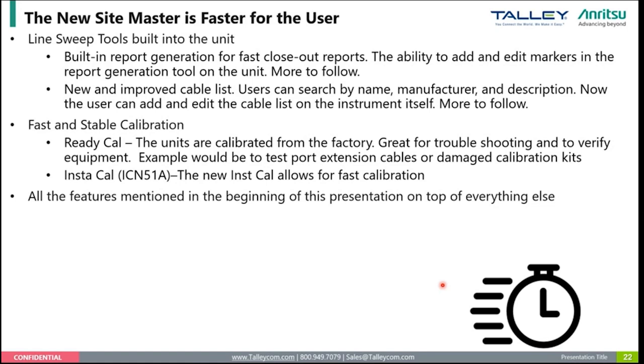With ReadyCal, you don't really need that, because now you can right off the bat do some form of measurement, get a ballpark if it's correct, then calibrate and see if the measurement is somewhat in the ballpark. So it speeds up your capability for a sanity check as well.